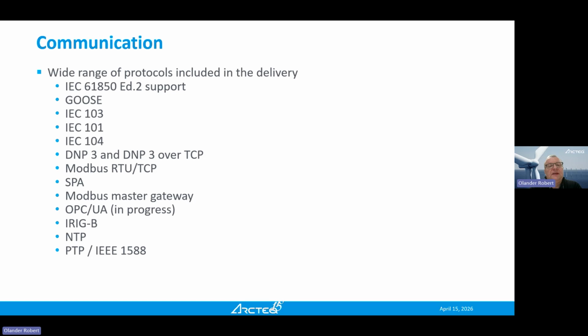Okay, GOOSE parallel communication, of course, is used more and more instead of copper signaling between the devices. Of course, then 61850 GOOSE can be used. Then we have a lot of other protocols which still are in use to some extent. 61850 is slowly replacing them, but we have IEC 103, 101, 104. Of course, 101 and 104 remote protocols are still very widely used.